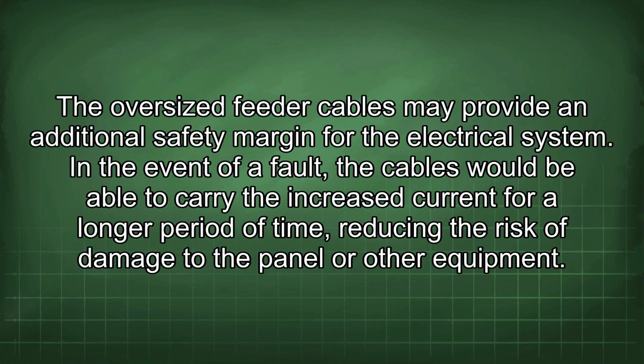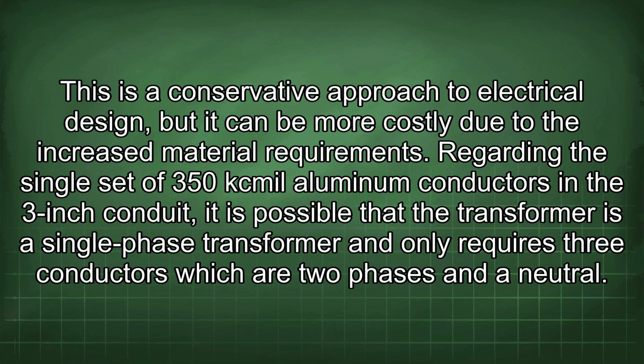The oversized feeder cables may provide an additional safety margin for the electrical system. In the event of a fault, the cables would be able to carry the increased current for a longer period of time, reducing the risk of damage to the panel or other equipment. This is a conservative approach to electrical design, but it can be more costly due to the increased material requirements.